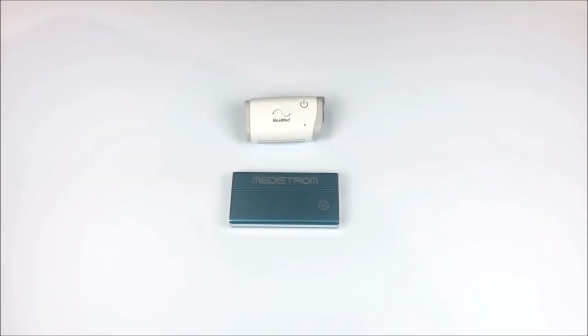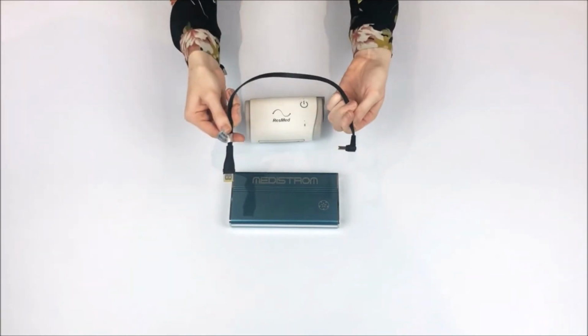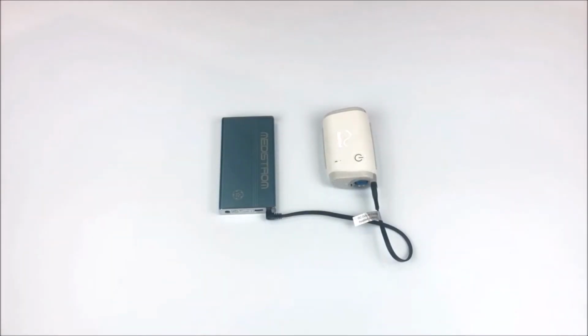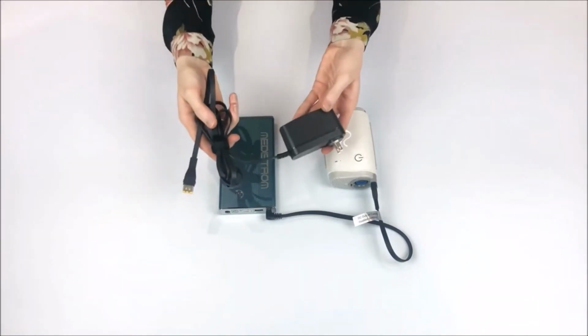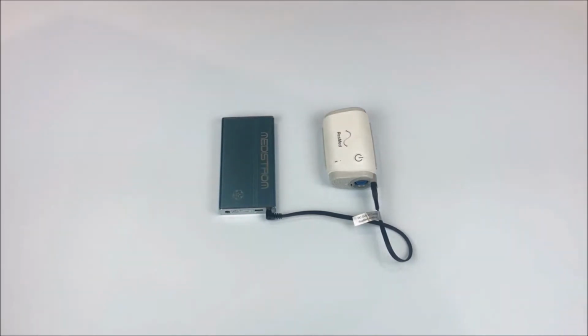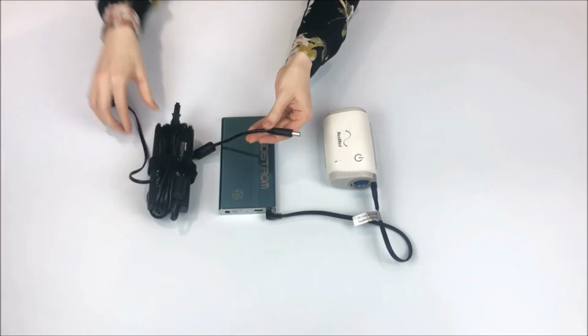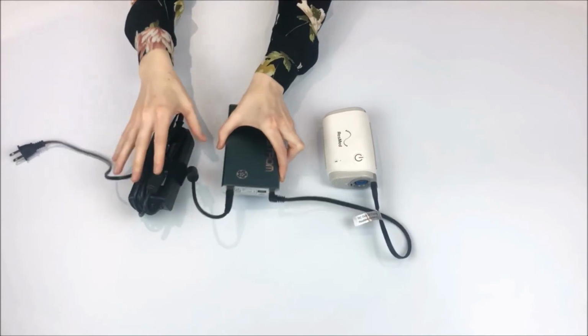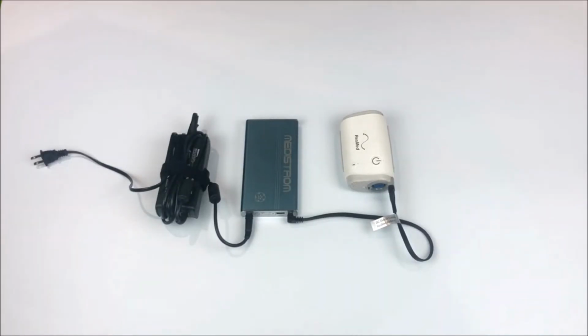To set the AirMini up with the battery as a backup, we'll use the DC cable to connect the battery to the AirMini. One thing to note when using the battery as a backup with the AirMini is that the AirMini power cord cannot be used to connect the wall power to the battery. The AirMini power cord has a lower output than most others, therefore is not able to be used with the battery as a backup. Therefore, we recommend that patients use either an AirSense 10 power cord if they have an AirSense 10, or purchase the Medistrom AC adapter. Here you will see the AirSense 10 power cord used to set the battery up as a backup.